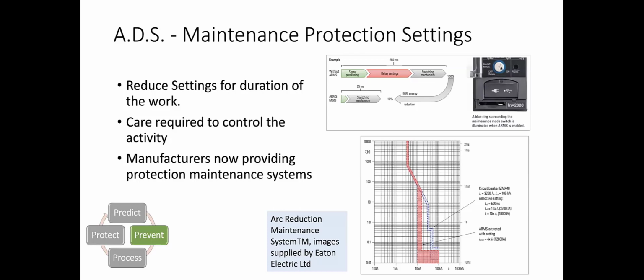So you can see in this particular case, I don't know if you can see my mouse in blue there, that's the normal setting, and the maintenance setting is in red. So in reducing the amount of time to disconnect a fault, it'll reduce the incident energy as I've described earlier.